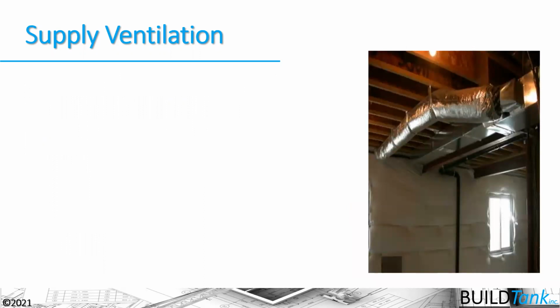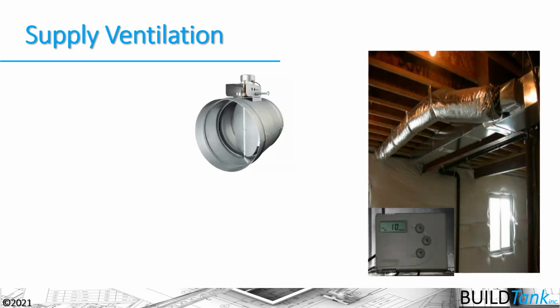Supply side ventilation often looks like this, where you have a duct run from the outside to the return side of the furnace, and you're using the furnace fan to bring air into the house. There's some type of control, if I'm not going to be running it continuously, that will turn my fan on to bring in air intermittently. And there's often a damper in that duct so that I can close it off when the furnace system isn't running, if I'm running it intermittently for that ventilation system.